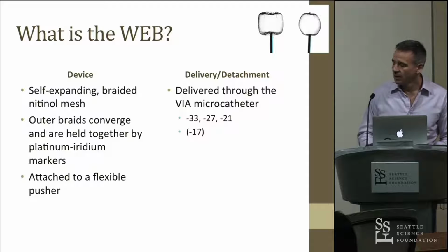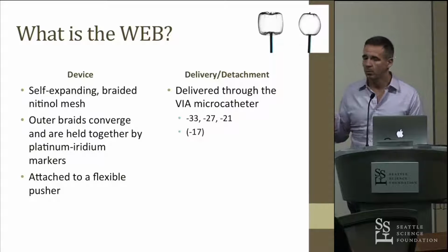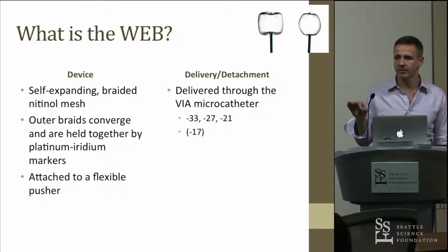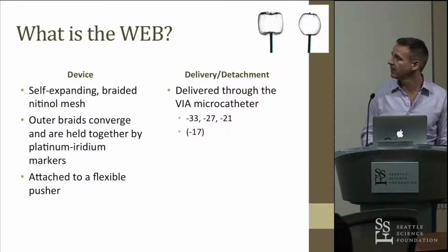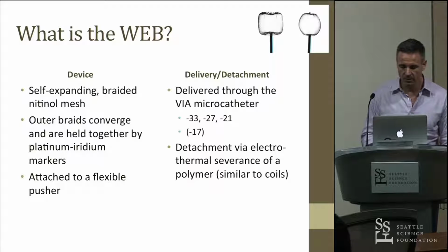And it's delivered through one of 3 catheters. So there's a VIA 33 for the big devices, so the 10 and 11 go through the VIA 33. Then there's the 27 and 21 devices that span down to smaller sizes all the way down to 3 millimeters. And then there's a 17 device that's coming. So soon we'll be able to deploy these ball type devices through catheters that are the same size that we're using now to coil aneurysms routinely. And I think this is going to be a pretty big advance in terms of what we're doing here. They're attached via an electrothermal severance of a polymer, so it's similar to the way that the MicroVention coils or the Micrus coils detach.